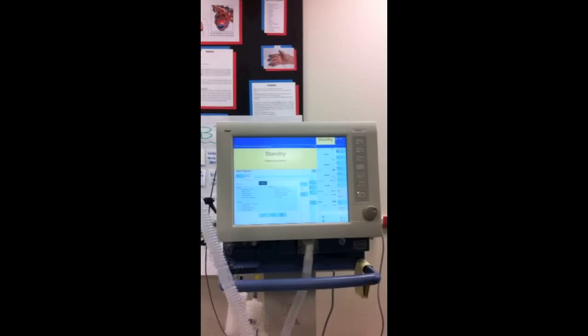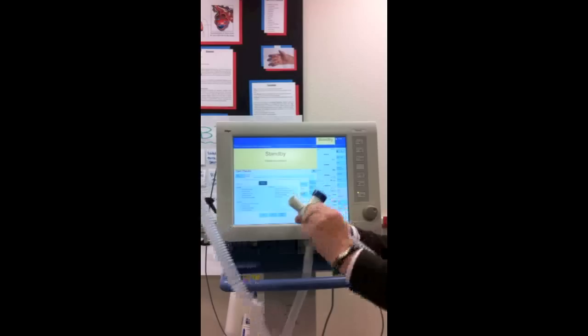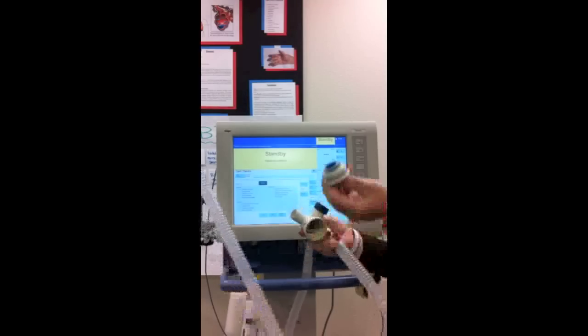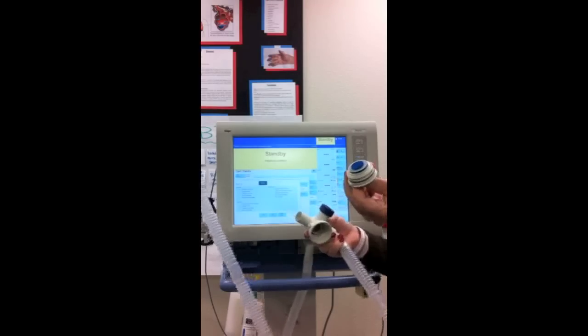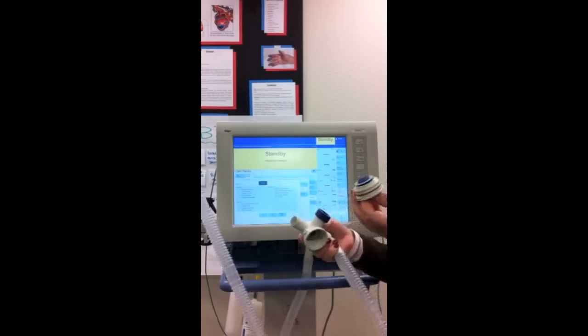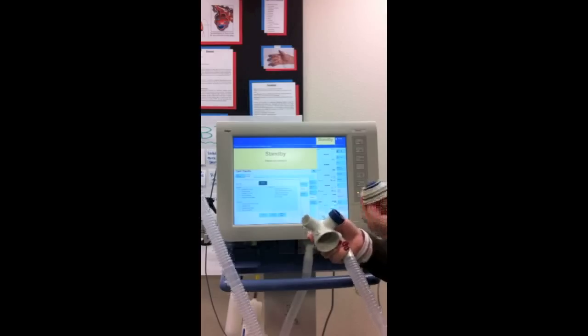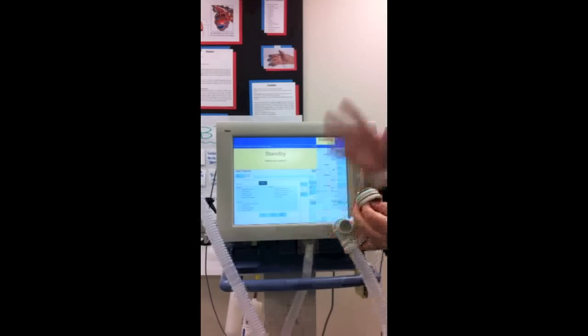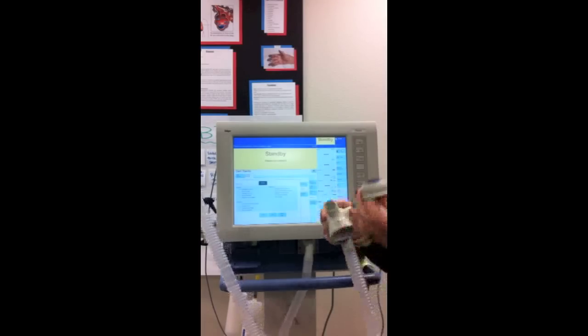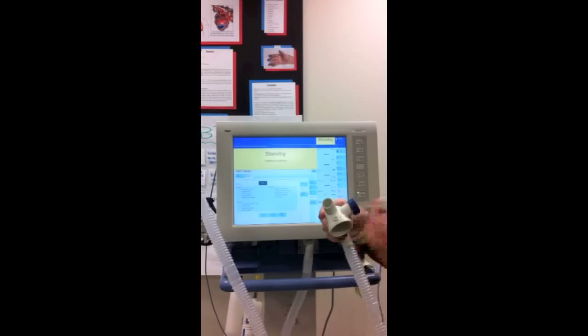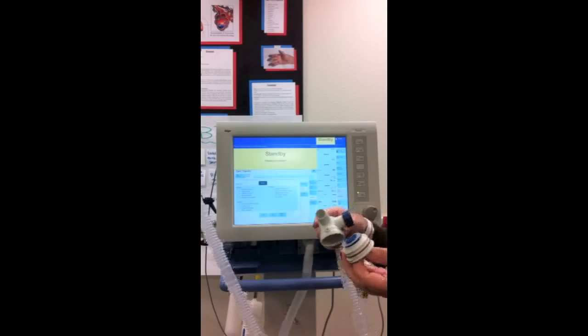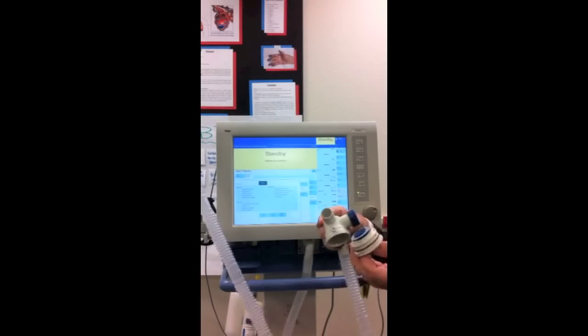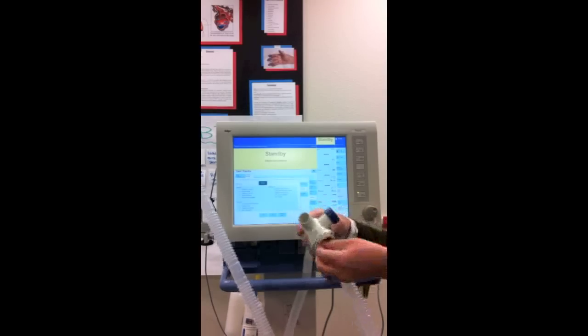You have to turn this to open it and find the mushroom valve in this one. If this is not tight enough, the ventilator won't work. It makes this obnoxious sound, kind of like the Ambu bag does when it makes that loud sound. This does the same thing. So if you're having problems with it cycling into inhalation and exhalation, you want to check this and make sure it's okay, that it doesn't have any moisture on it or that this is screwed in tight enough.